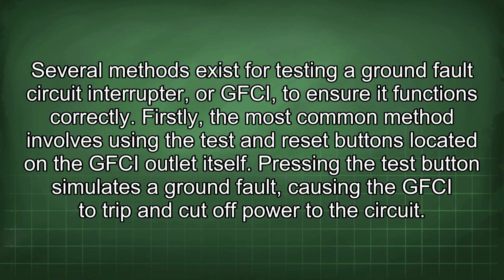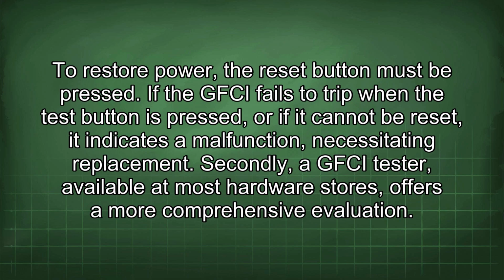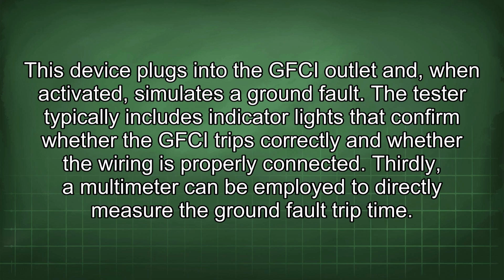Several methods exist for testing a ground fault circuit interrupter, or GFCI, to ensure it functions correctly. Firstly, the most common method involves using the test and reset buttons located on the GFCI outlet itself. Pressing the test button simulates a ground fault, causing the GFCI to trip and cut off power to the circuit. To restore power, the reset button must be pressed. If the GFCI fails to trip when the test button is pressed, or if it cannot be reset, it indicates a malfunction, necessitating replacement. Secondly, a GFCI tester, available at most hardware stores, offers a more comprehensive evaluation. This device plugs into the GFCI outlet and, when activated, simulates a ground fault. The tester typically includes indicator lights that confirm whether the GFCI trips correctly and whether the wiring is properly connected.